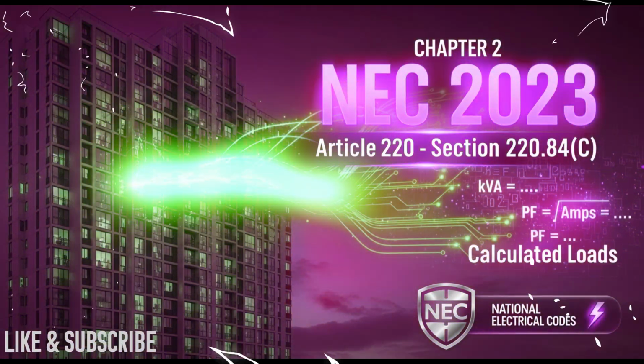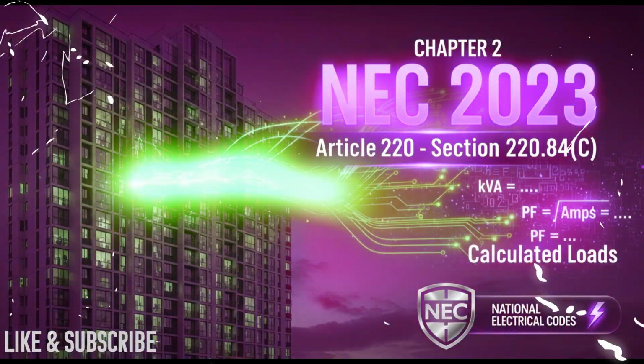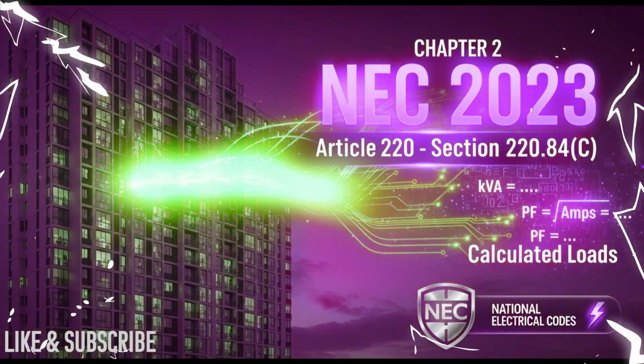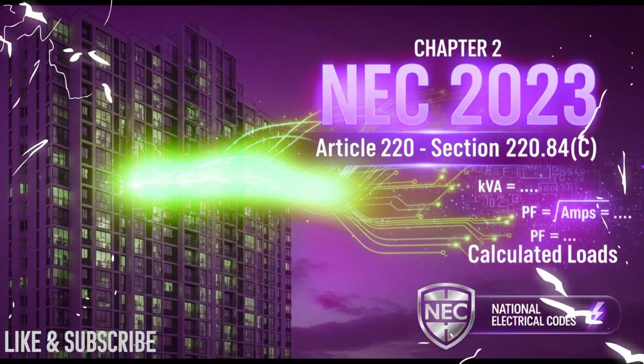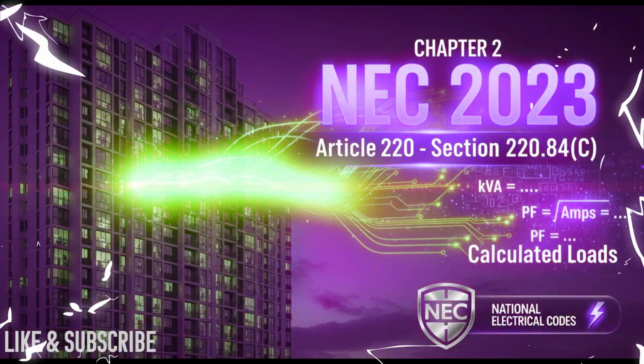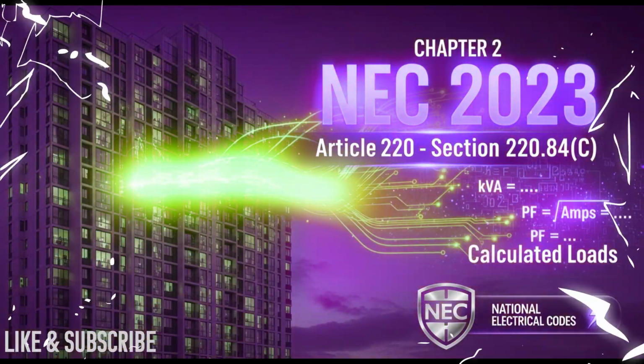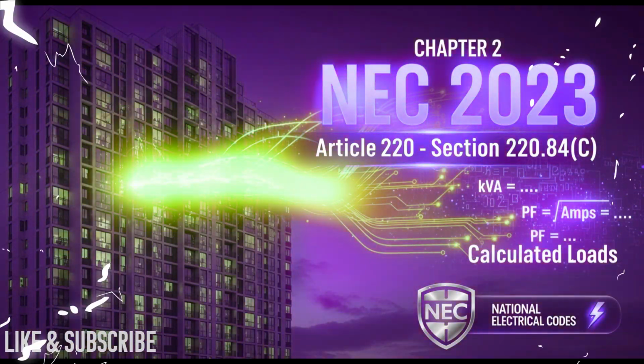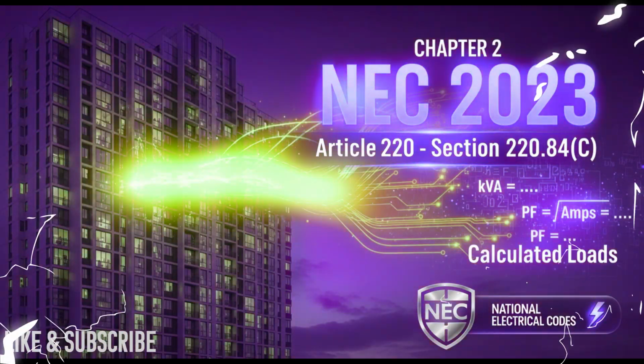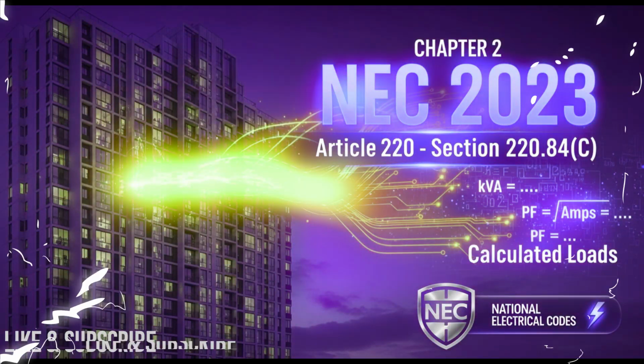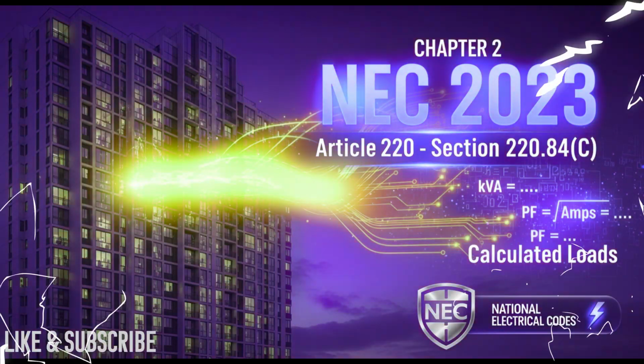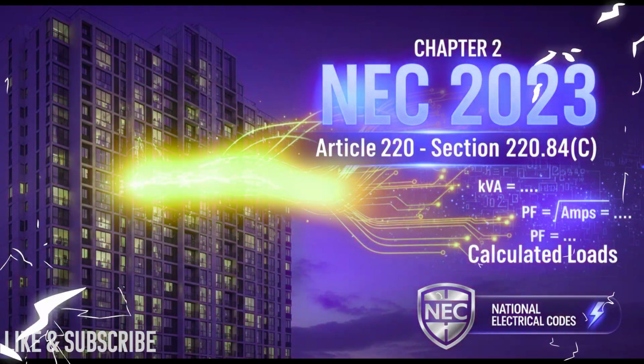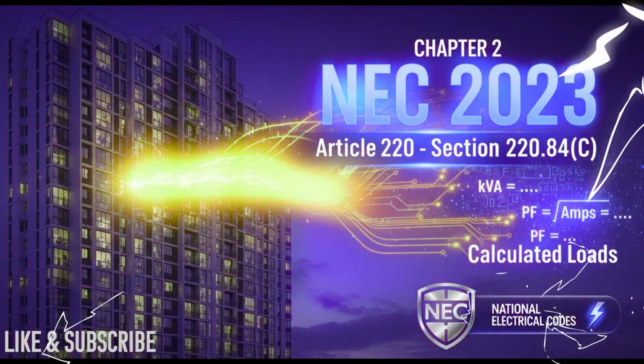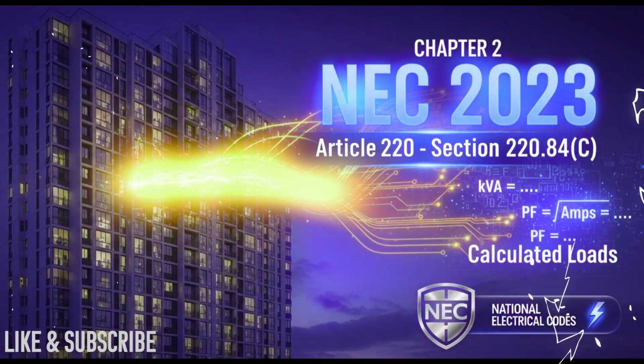So that 3 VA per square foot isn't about the typical load with LEDs. Right. It's about ensuring the wiring, the protection, the infrastructure can handle a potential maximum load dictated purely by the dwelling size, period. It builds in that safety margin regardless of the tech being used right now. Okay, that makes sense. A universal safety net baked into the square footage. Couldn't have said it better. All right, so we've got the baseline for lighting and general outlets calculated based on area.